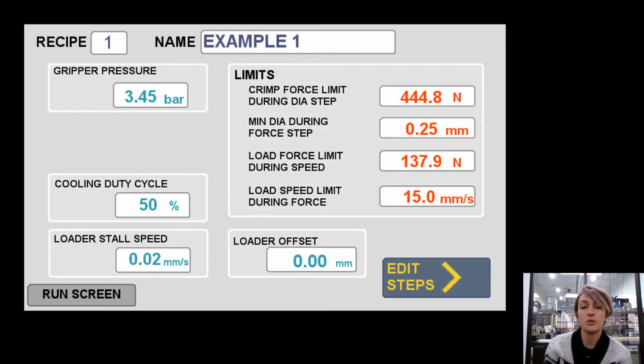Before we go back to the recipe that we just programmed, let's back up a step to the general recipe settings screen that we were on earlier, because I mentioned that we would come back to this box of limits. Now that we've talked about the step types, we can talk about these limits. Remember I said that if you choose to control the diameter of your station, then it will crimp with whatever force is necessary to reach that diameter. However, it's likely you're going to want to limit the force that your stent experiences, and you would do that here with this setting. If you have a crimp force step and you're controlling the force of your station, you may want to also put a minimum limit on your diameter, in which case you would set that here.